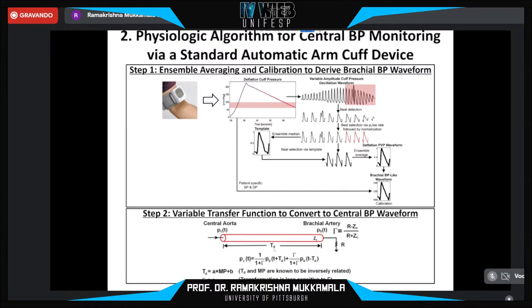The second step is to take a transfer function and apply it to this waveform to convert it to the central blood pressure waveform near the heart. The transfer function is defined by a tube load model of wave reflection with parameters indicating the pulse transit time and wave reflection coefficient. The wave reflection coefficient is set to a nominal value, as the transfer function is typically insensitive to that parameter. But the pulse transit time is a crucial transfer function parameter, and it is determined based on its inverse relationship with mean blood pressure. This way, the transfer function can vary within a patient and from patient to patient.